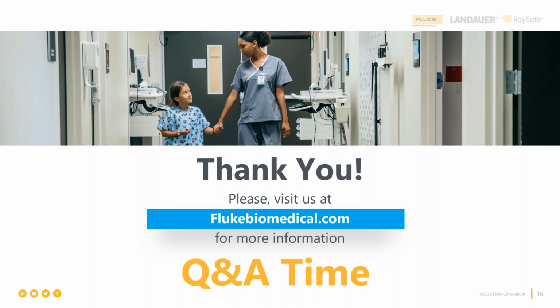So it's really determined by the situation in which we need to make the measurement. They can all be accurate in terms of the way the measurement is made, but it's on us, biomedical engineers and technicians around the world, to ensure that the measurement device, whether it's the analog gauge, the mercury column, or the oscillometric automated technology, is safe and effective for clinical use. That's our job. And the way that we do that is prescribed, and that's why we're doing the training here.